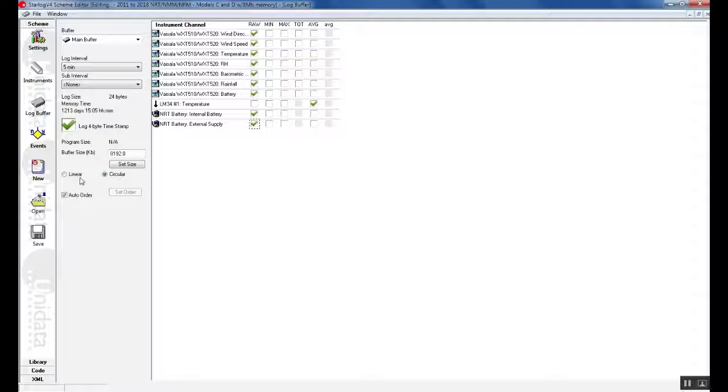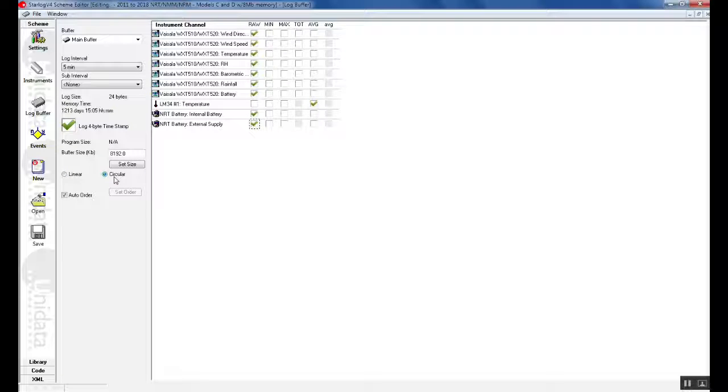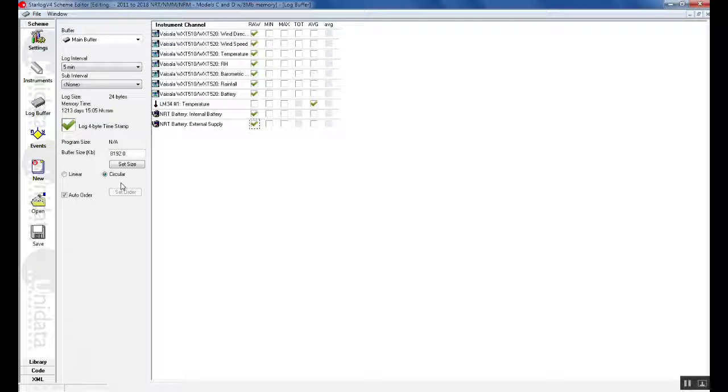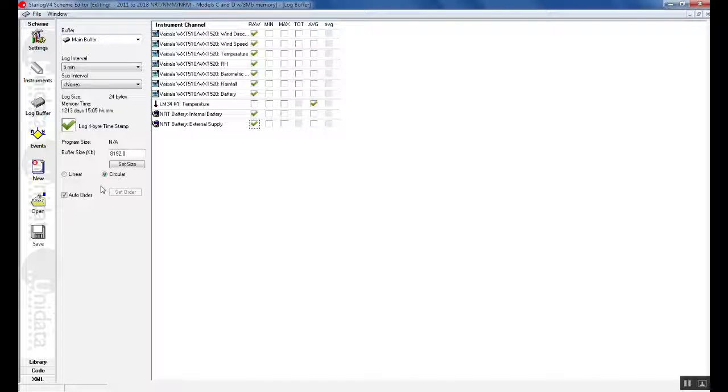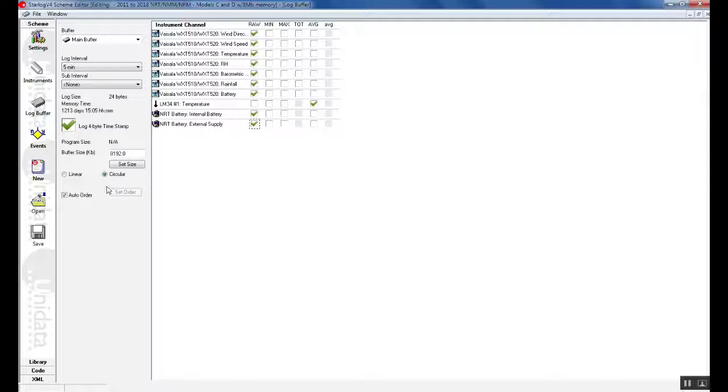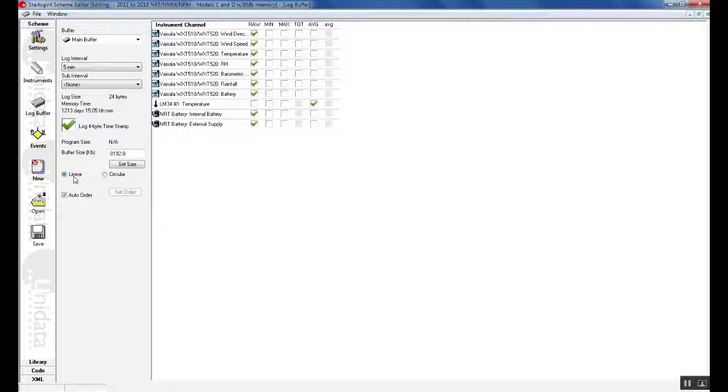With an 8 meg scheme the buffer size of the NRT is approximately 8 megabytes. There is also a setting of linear and circular. With NRT schemes it is set to circular. This indicates that once the memory is full it will wrap around again and start overriding previous memory. This is always done with an NRT scheme as the data is sent to the server at a predefined interval and then this is saved on the server. If you are using another logger such as a Starlogger which does not send data to the NEON server we can click on linear. This would indicate that once the memory is full it will stop logging.